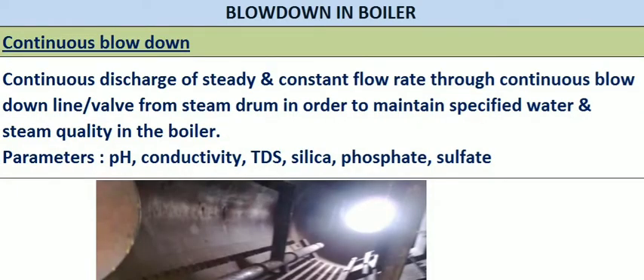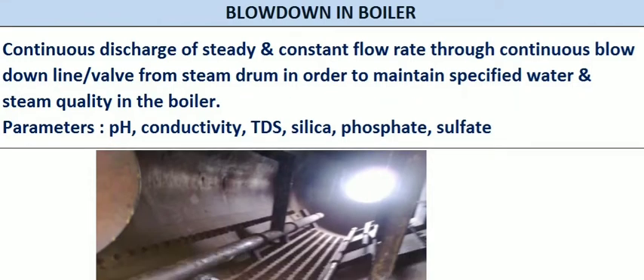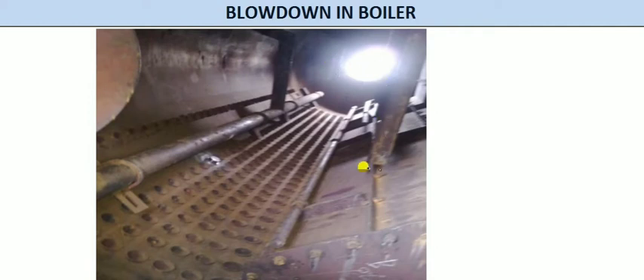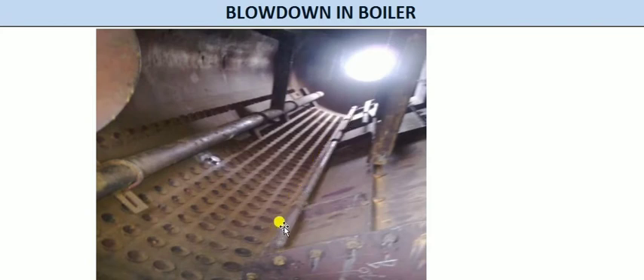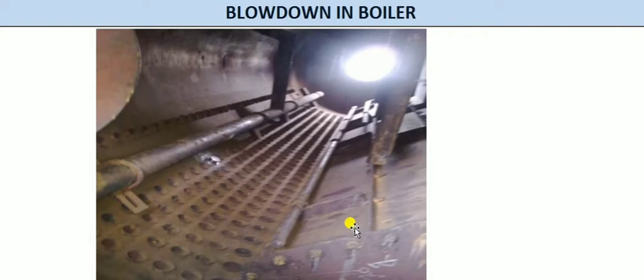The continuous blowdown is taken from the steam drum. This is the typical steam drum in the boiler — the water wall tubes are projected and welded into the steam drum. There is a feed water pipe and a continuous blowdown pipe, which is a perforated pipe with holes. This line is connected to the drain system and goes to a flash tank. We cannot directly drain it because the steam drum pressure is there; it needs to be flashed out and goes to the blowdown vessel.